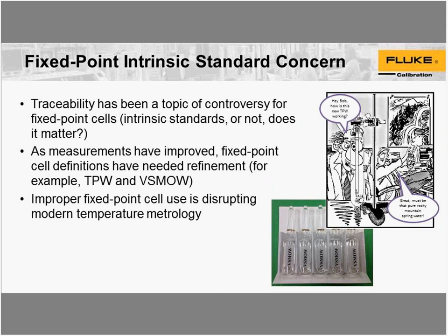So, fixed point cells have been considered intrinsic standards as they are chemical realizations of a consistent and repeatable temperature, linked to a constant in nature through their chemistry. But there is some controversy with fixed cells, or some inconsistencies as well.